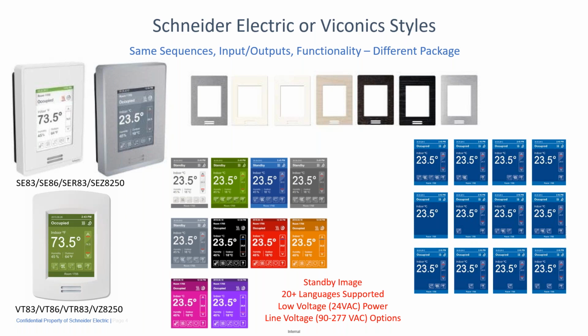Likewise, over here on the right part of the screen, another configurable option is what you want to show on the screen. You can have all the buttons available and change the mode: heat, cool, auto, off; change the fan: low, medium, high, auto; and a degrees C, degrees F toggle button. And there's a language button. The controllers support 20 different languages. So if you put it into a dorm room situation or a hospitality situation and the person in the room speaks Spanish or French, they can toggle to have that language show up.